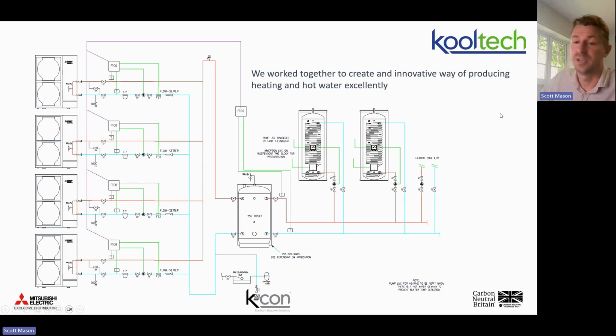That's a more detailed version which shows how you would actually apply that application and how all the controls philosophy and everything works. And these drawings are obviously available. So if anyone has a project like this, then just reach out and we can make this happen. One of the reasons people also like this style of arrangement sometimes is because with indirect vessels with a pasteurization regime, you can have multiple points of failure, you can increase your volumes, you can do loads of good things with our range of indirects. But it just means there are some external considerations to make that can't be controlled by the heat pump.